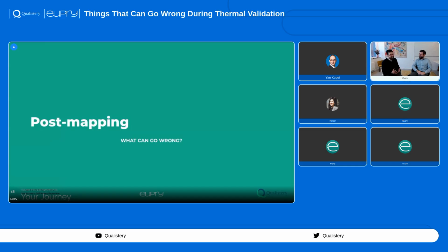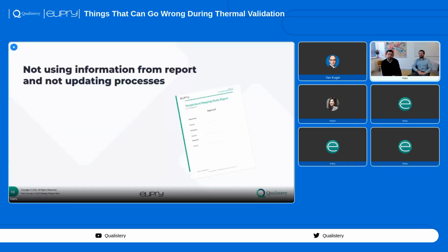Yeah. But there are still things that can go wrong, unfortunately, afterwards as well. We have experienced that people do not use the information from the report afterwards, and do not update the processes. The whole point of the mapping, the thermal validation, is to pinpoint how good the facility is, but also to pinpoint some hot spots, some cold spots, some places in the large facility that you have to be more aware of. So these conclusions and information need to be acted upon. That could be a fixed monitoring system after the mapping process to constantly monitor your facility, using the recommendations from the report to choose the positioning of the monitoring loggers.